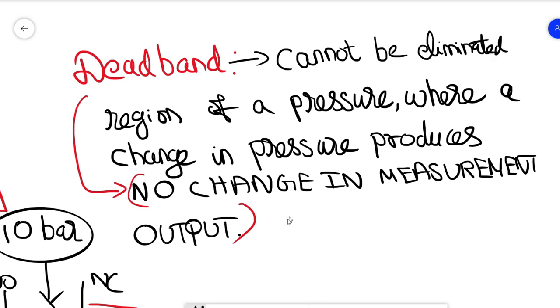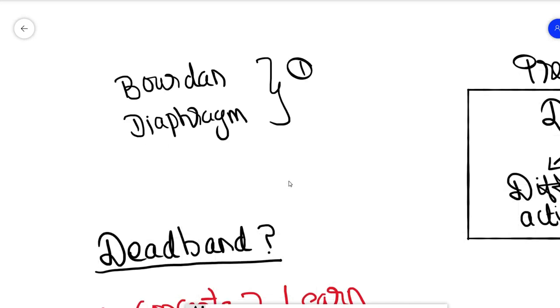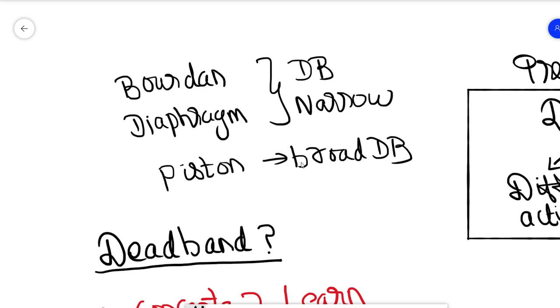Normally, a Bourdon tube and diaphragm switches typically have narrow deadband, while piston switches have broad deadband. So we have to choose wisely on this pressure switch depending upon the minimal deadband as per the process requirement.